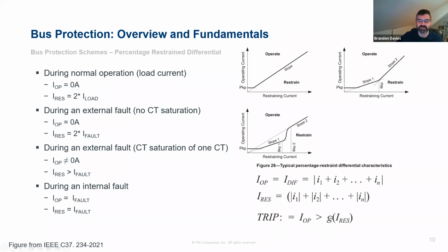So you're usually in that 60 to 80% range is what you typically expect to see for the slope characteristic here if you're using a single slope. So I guess any questions on the stuff I've gone over so far? Again, I'm covering a lot of ground on this, but it's trying to get some exposure to some of the different options out there.